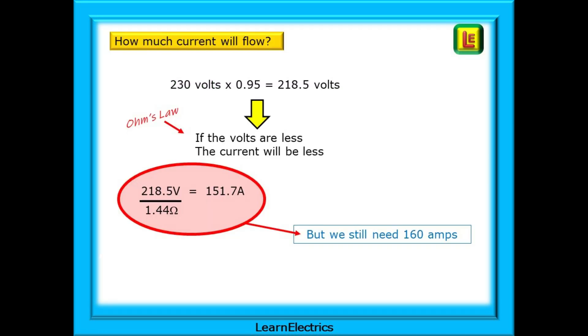The next question is if the voltage is dropped then by how much has the current dropped? Taking our 230 volts nominal voltage and multiplying by 0.95 we get 218.5 volts as the low figure. If the volts are less the current will be less. 218.5 volts divided by 1.44 ohms is just 151.7 amps. Not close enough to the 160 amps that we need. We're not going to meet the requirements for disconnection times. We need to do more.